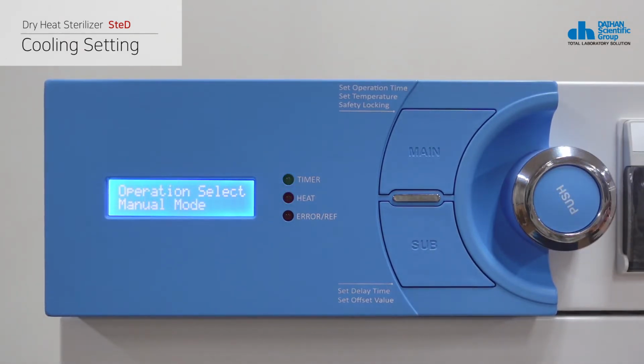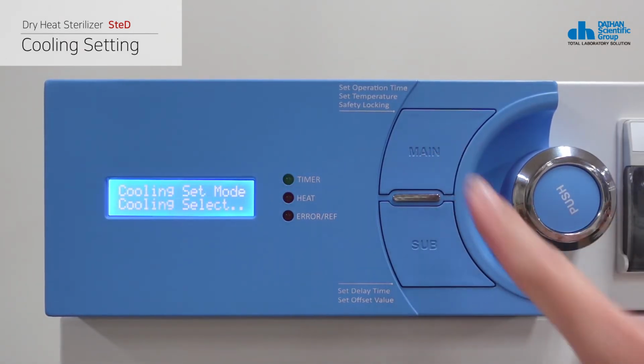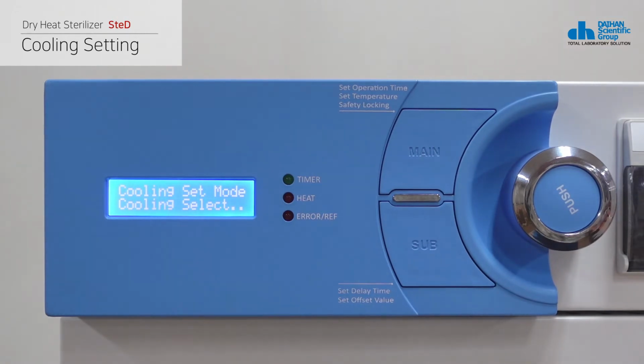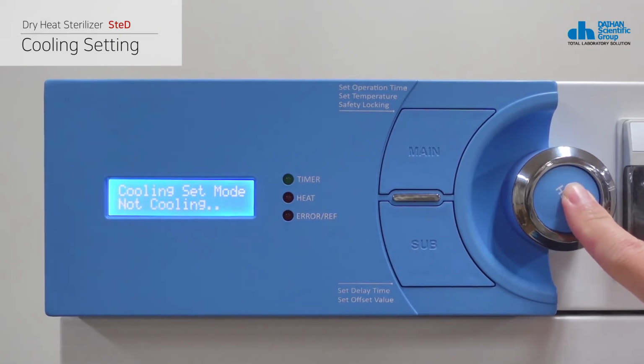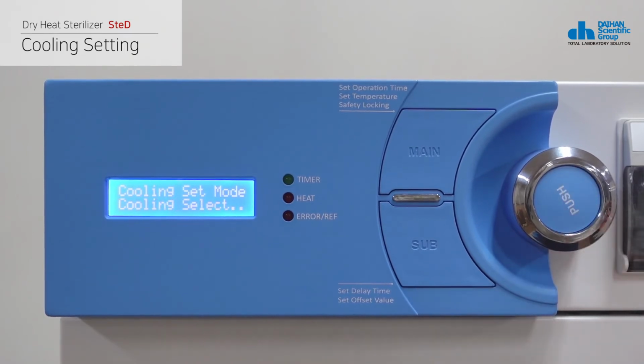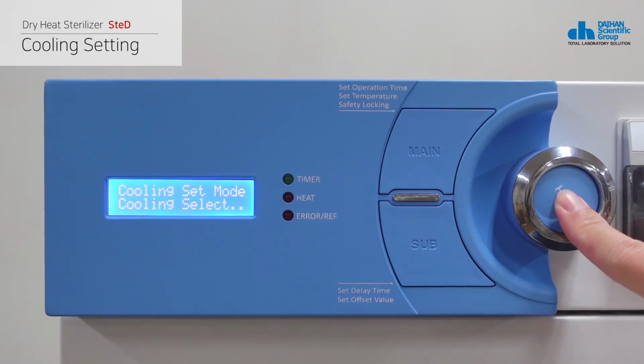Press the main button in manual mode to enter cooling setup mode. The cooling setup mode is the mode in which the cooling fan is set to operate after the sterilization operation is completed. Pressing the push button in the cooling setting mode changes the setting to cooling select or no cooling. If you press and hold the push button after the setup is complete, the screen flashes and saves the setup.